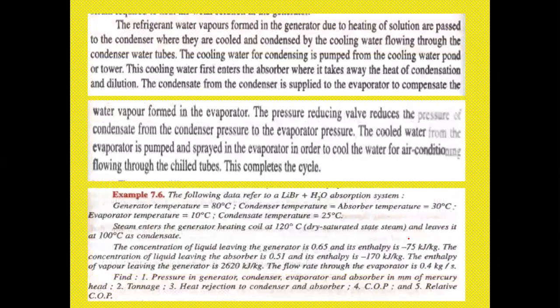Now, the refrigerant water vapors formed in the generator due to the heating of the solution are passed to the condenser, where they are cooled and condensed by the cooling water flowing through the condenser water tubes. The cooling water for condensing is pumped from the cooling water pond or tower. This cooling water first enters the absorber, where it takes away the heat of condensation and dilution.